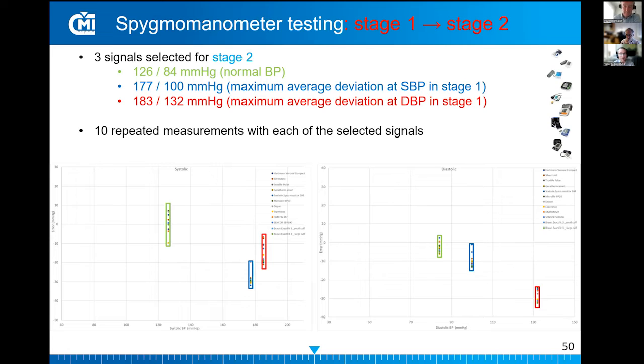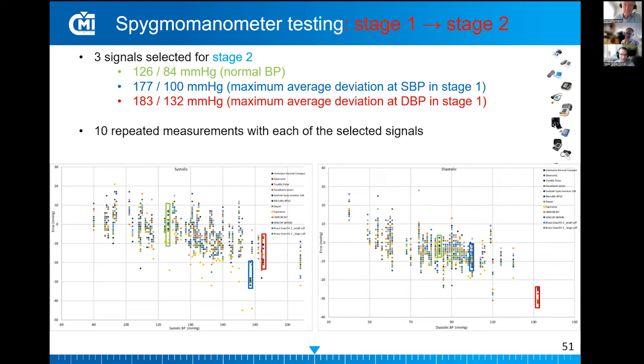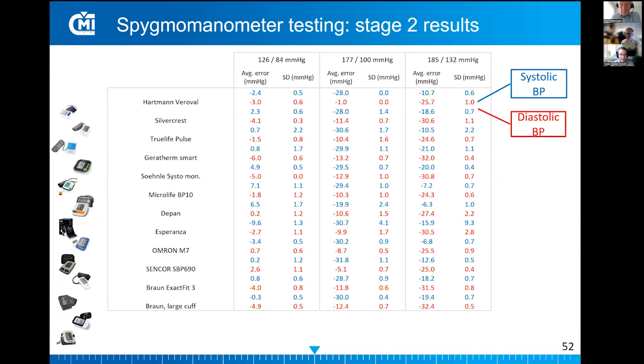This one was selected because it had the highest average deviation of systolic blood pressure across all devices in the first stage, and the second signal, 183 millimeters over 132, was selected due to the highest average deviation of diastolic blood pressure measurements in the first stage. 10 repeated measurements were performed with each device, and each of these signals, again, after adjustment and calibrations, are the signals in the scope of the testing. And here are the results. They are divided by systolic and diastolic blood pressure reading.